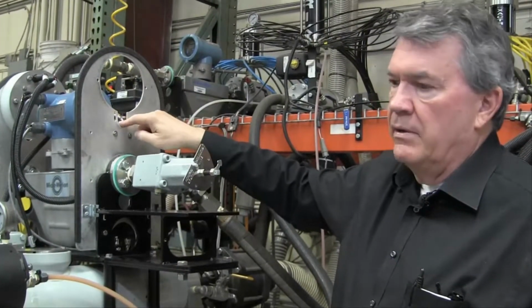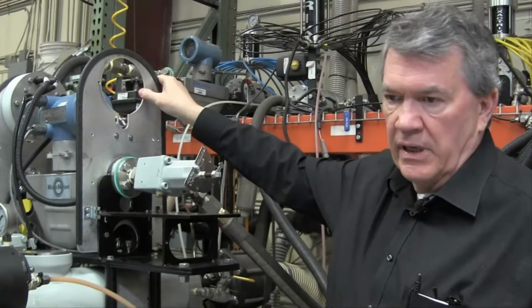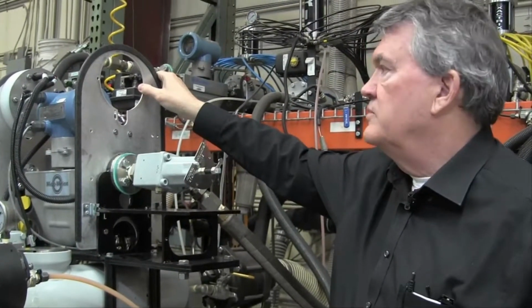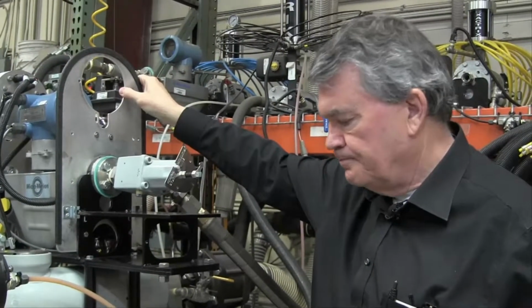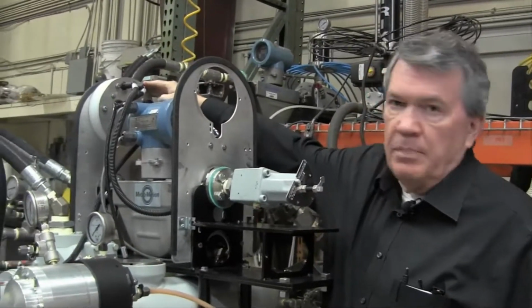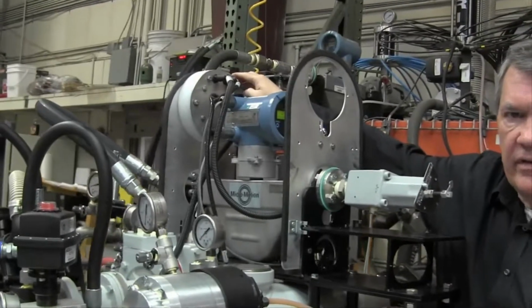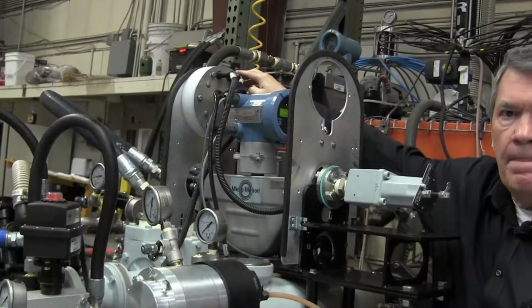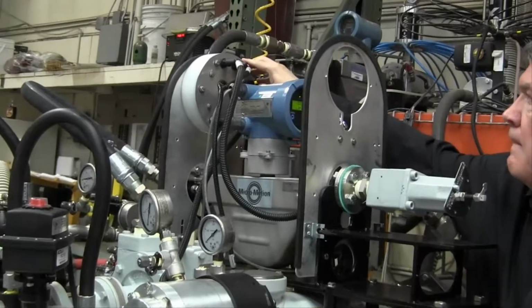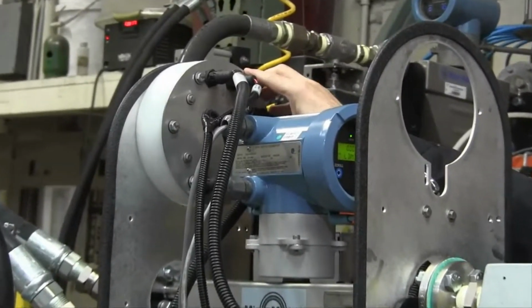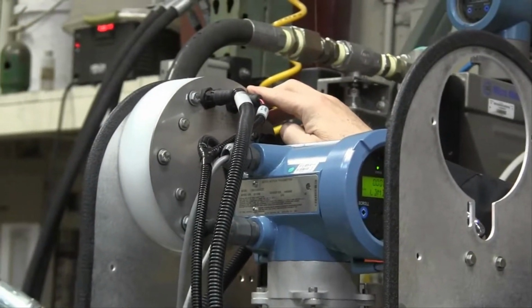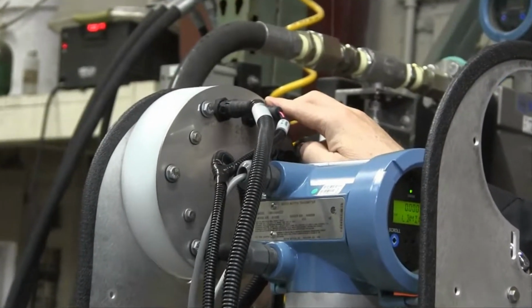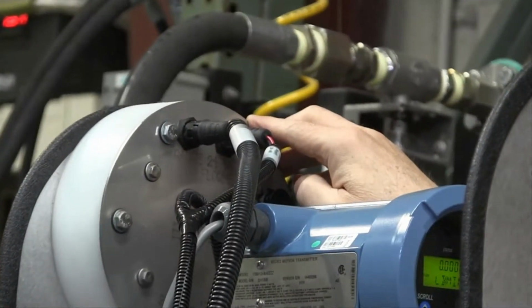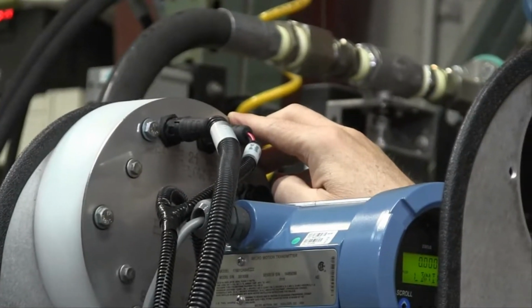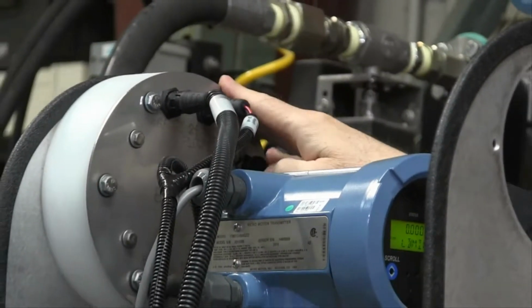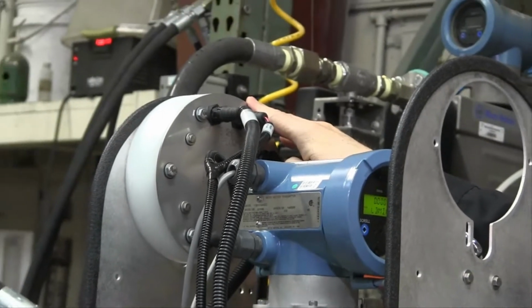This is also a voltmeter here that double checks the voltage, making sure we're getting the correct voltage to the electronics on the system. This is the power supply for the unit up here for the mass meter, and so this power supply can actually run 2 or 3 mass meters, and so in some cases we have other systems that have mass meters on them, and they're getting ready to send their signals on up to the controller too. So you can run 2 or 3 mass meters off of this one power supply.